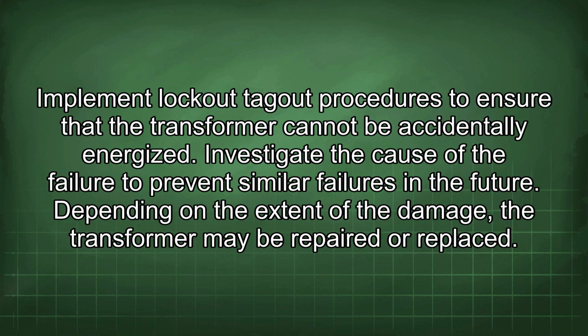Implement lockout-tagout procedures to ensure that the transformer cannot be accidentally energized. Investigate the cause of the failure to prevent similar failures in the future. Depending on the extent of the damage, the transformer may be repaired or replaced.